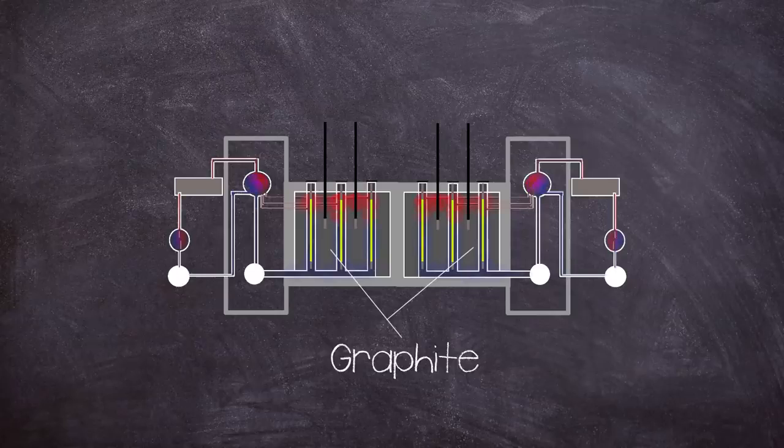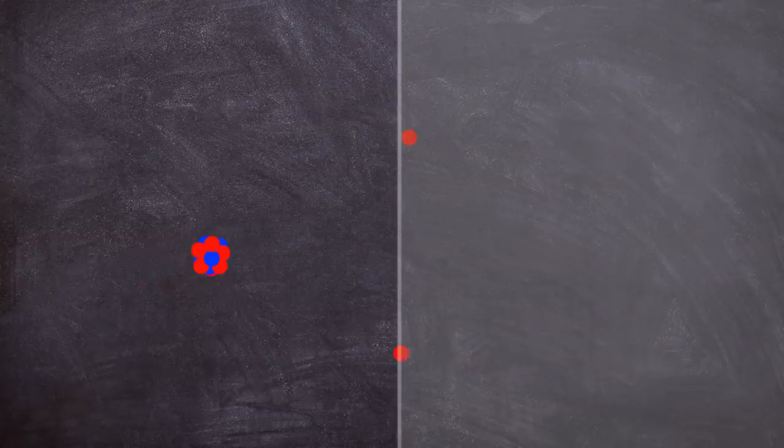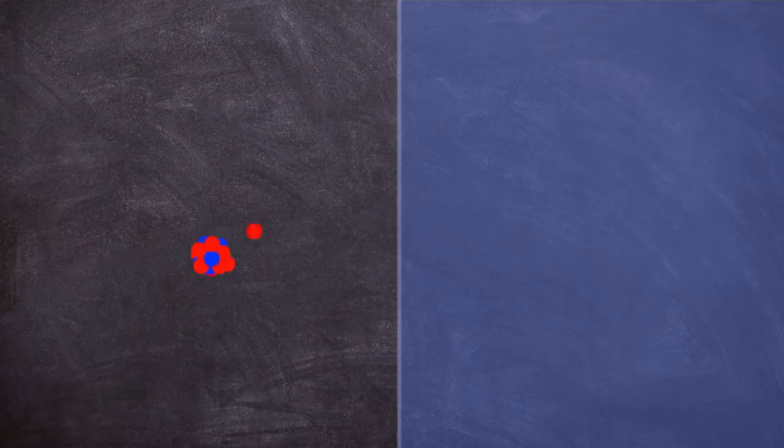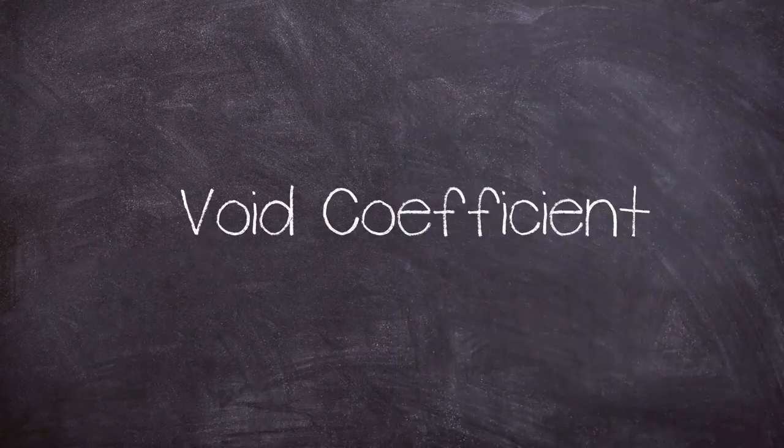As mentioned before the reactor employed graphite blocks for its moderator. Now a moderator is used to reduce the speed of fast neutrons released from fission, so they can better facilitate a chain reaction getting more use out of the fuel. Ideally moderators work without capturing any neutrons leaving them as thermal neutrons. But where the design has its potential flaw is having a separate coolant that can also absorb neutrons which can make the reactor unstable in certain situations. This brings up the big elephant in the room and that is void coefficient.